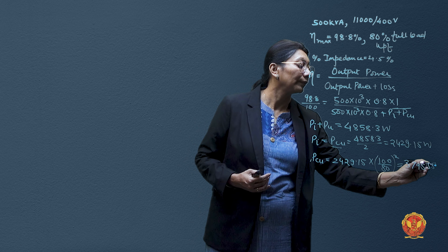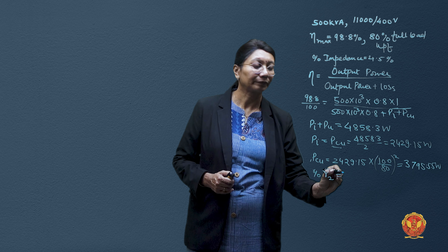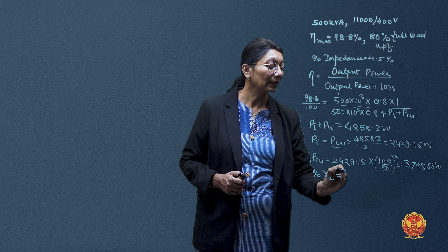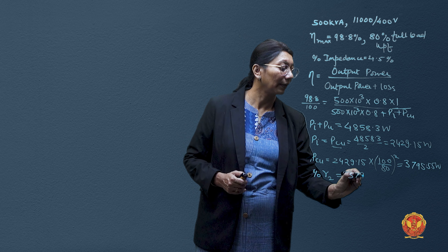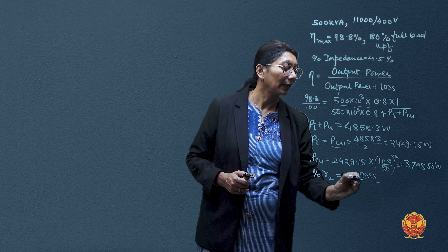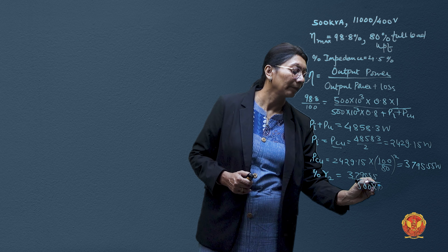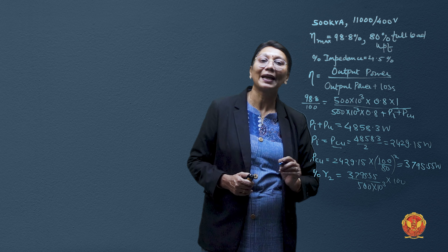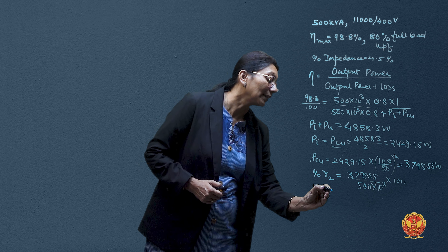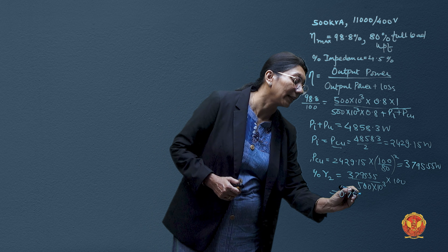From the copper loss, we can find the per-unit and percentage resistance values. The base is 500 kVA. So percentage resistance R% = (3795.55 / (500 × 10³)) × 100 = 0.759%. We also have the percentage impedance of 4.5% from the given data.